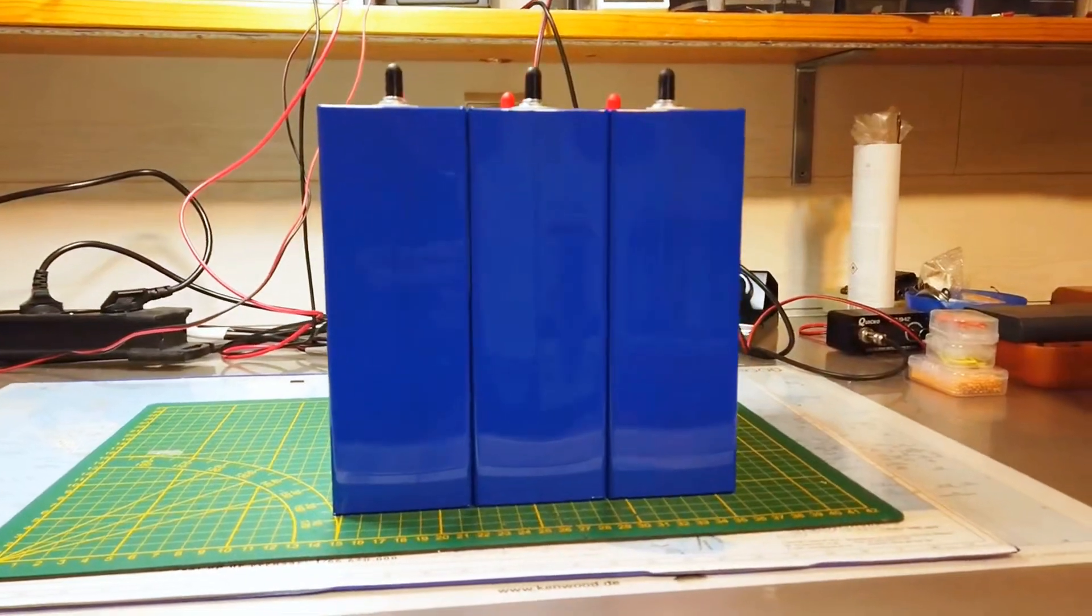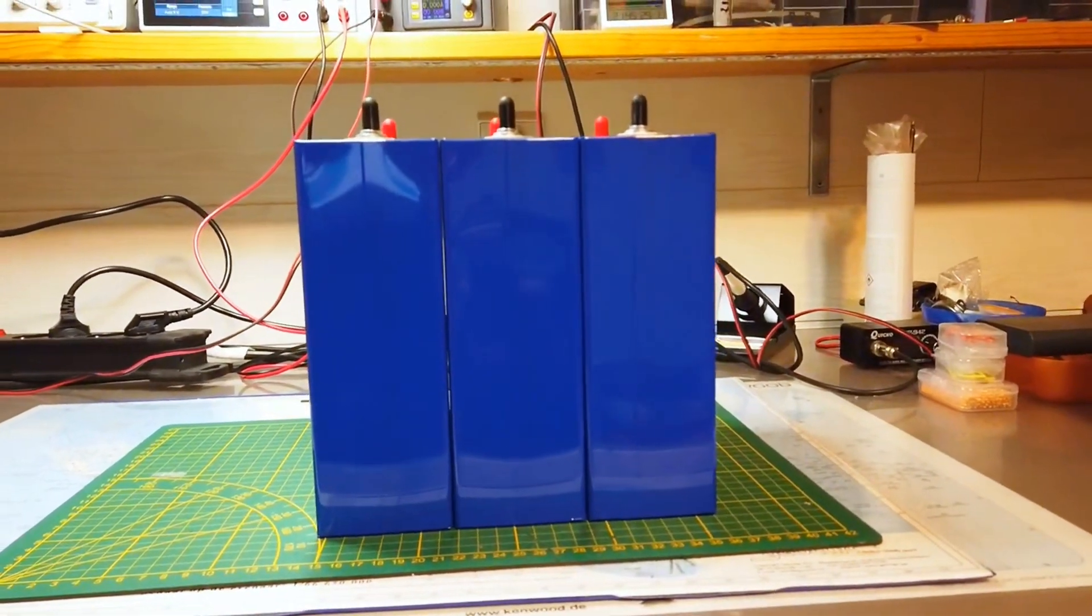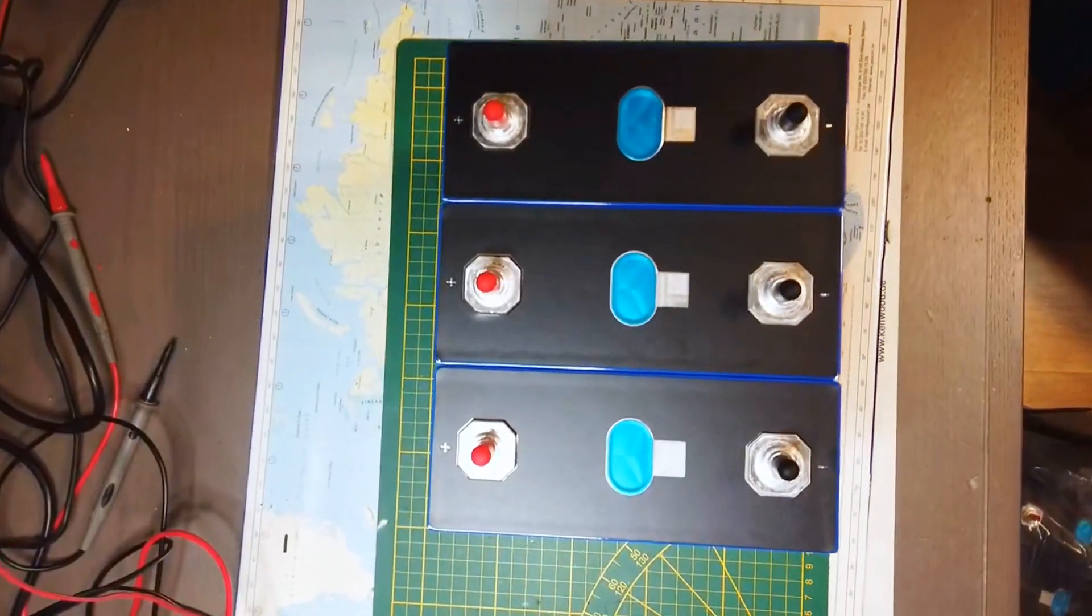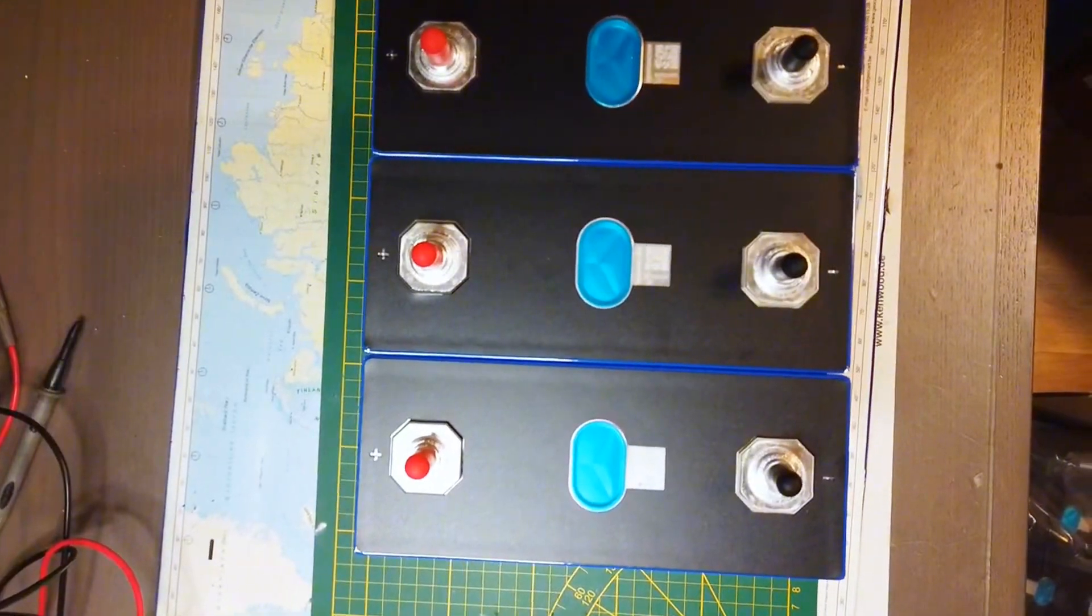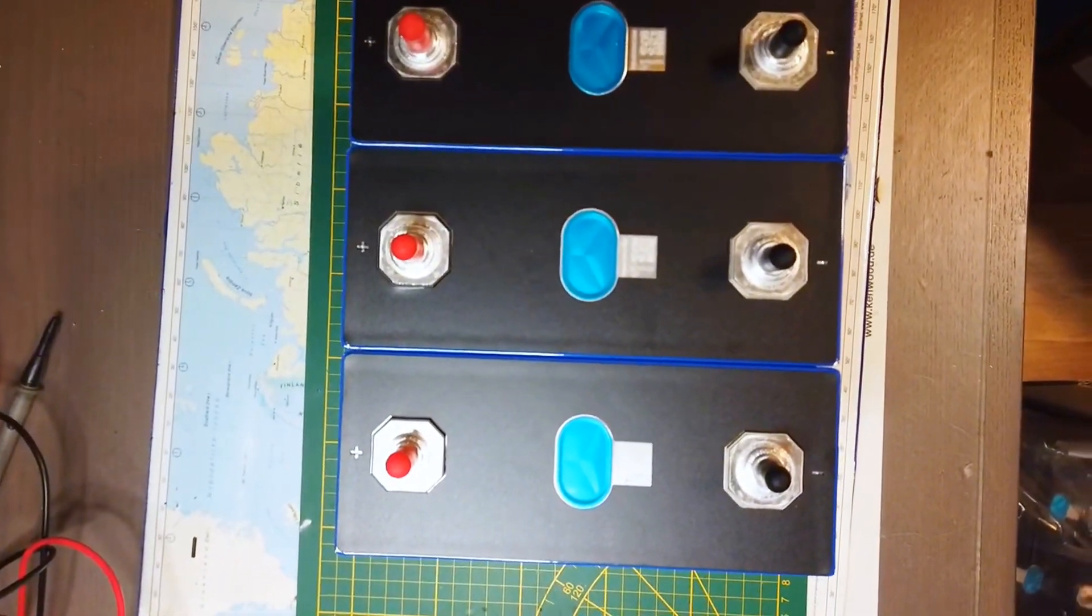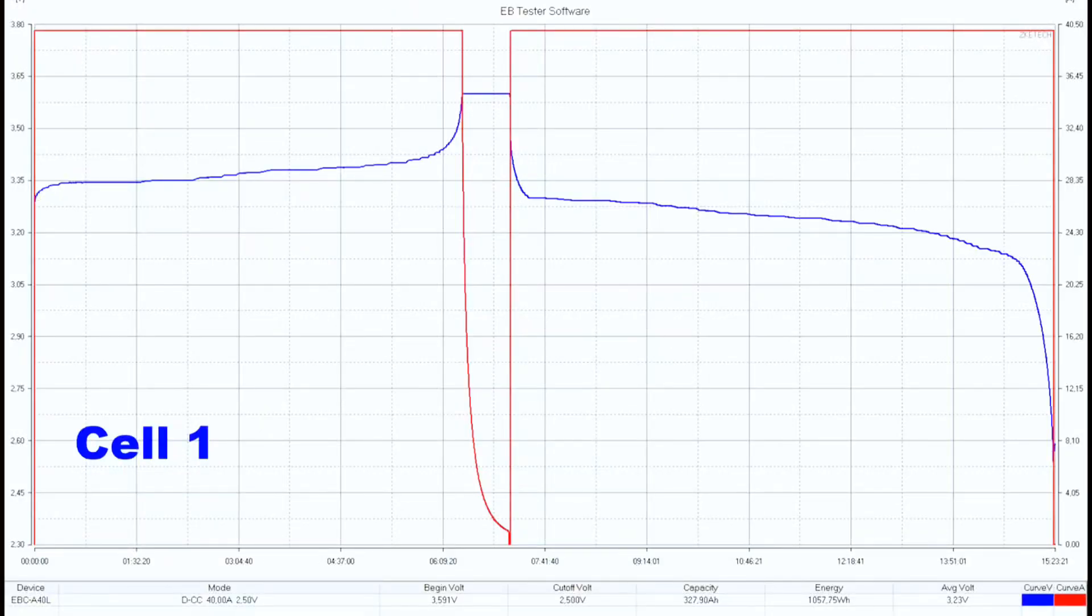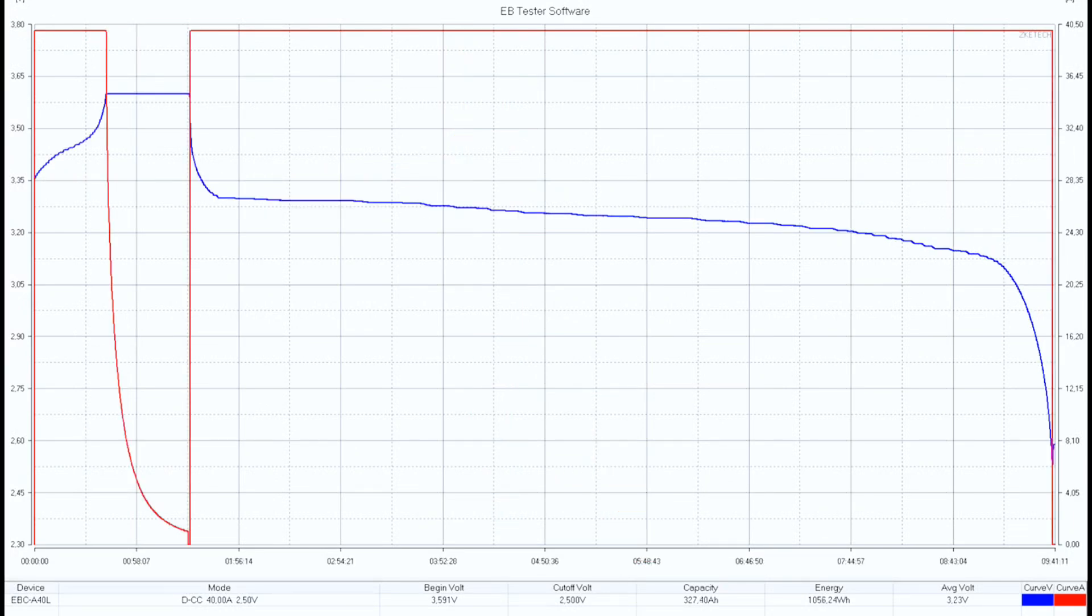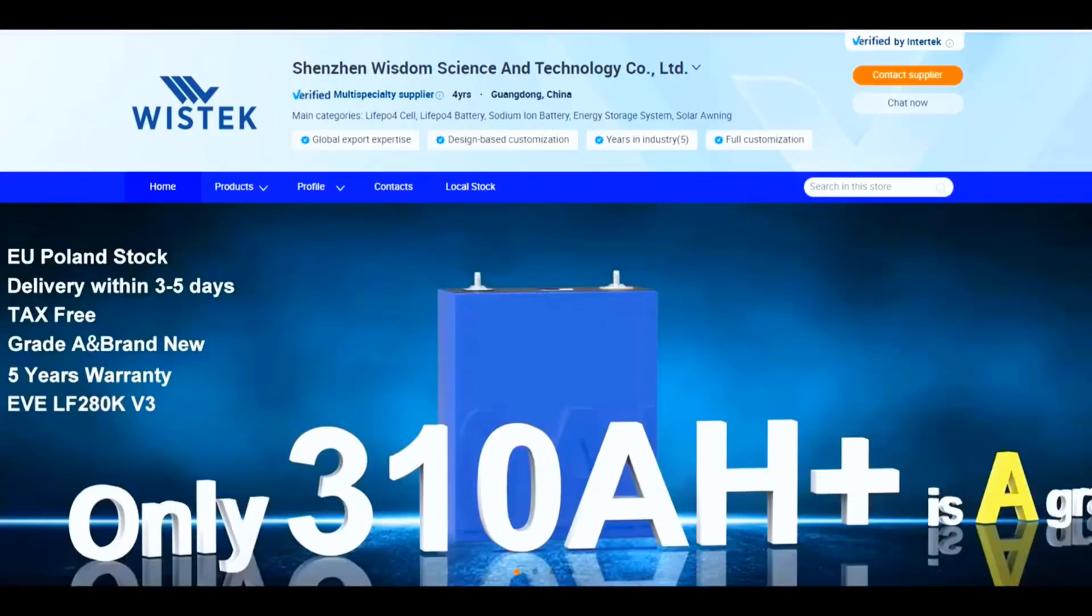The discharge curves look very similar. The MB31 cell shows capacity of 327.9 and 327.4 amp-hours. Both manufacturers under-promise and over-deliver. Wistek report: they sell great cells.